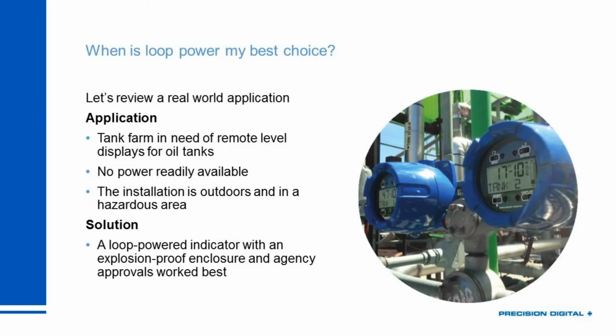They wanted to be able to display that storage tank information, but they didn't want to have the operators have to be next to the actual tanks to see it. It's a hazardous area in oil and gas, so they don't just have access to all of their wiring everywhere. It's expensive to run, and they need to run it through special conduits. So they didn't have power wires available where the operators wanted to see the level.